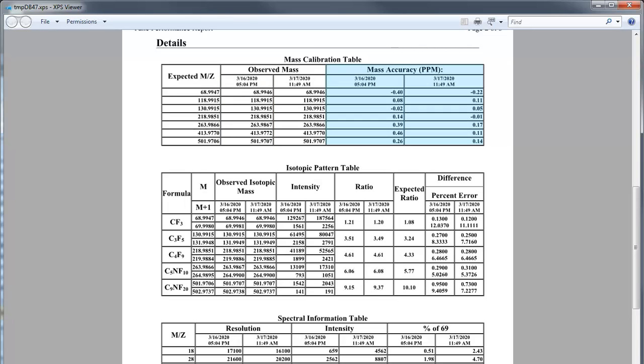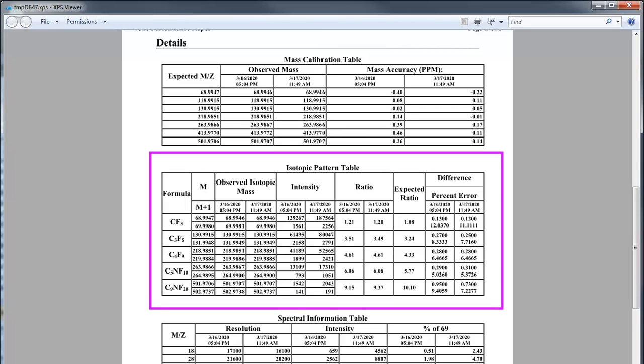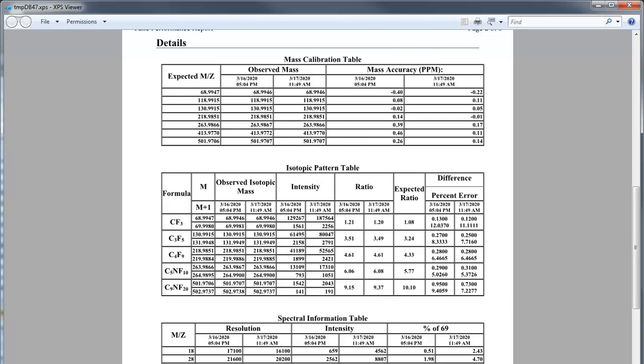The mass accuracy RMS is the mass accuracy calculated based on the masses listed in the mass calibration table in the MS method. The isotopic pattern table is a representation of the proper fragmentation patterns of PFTBA analyzed during the tune validation. The table calculates the ratio between the C12 and C13 and compares it to the expected values based on the known abundance of C12 to C13.